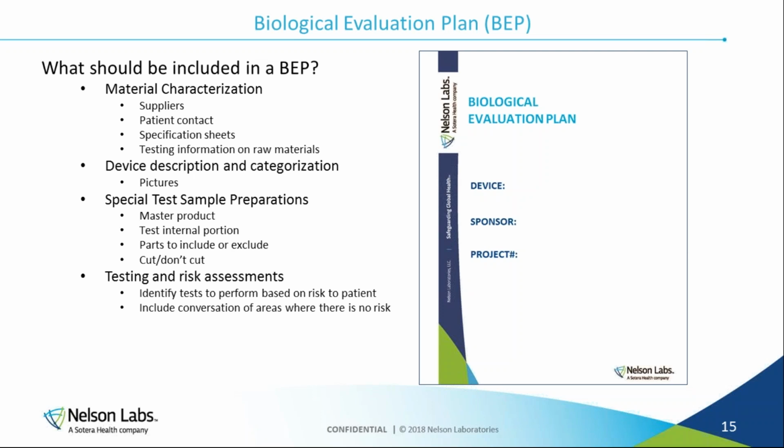And then we'll talk about testing and risk assessments, where we'll outline the specific tests. If we need to do particulate testing, we don't just say do particulates according to the standard. We actually will specify the method, the standard that's going to be followed, and give specific details, so that when you submit your device for testing, we've made all the decisions up front, and now it's time to just get the work done.